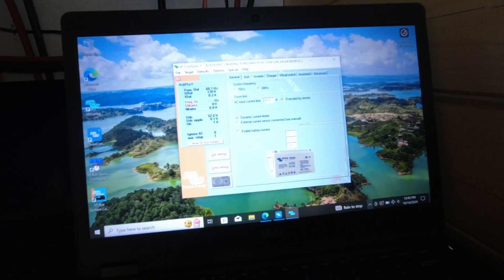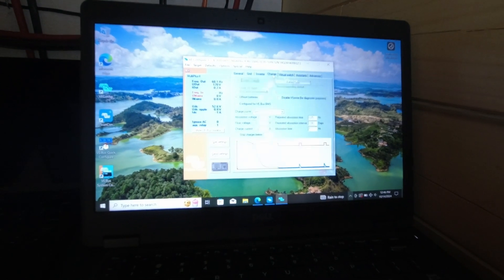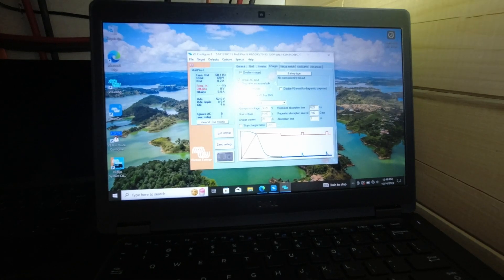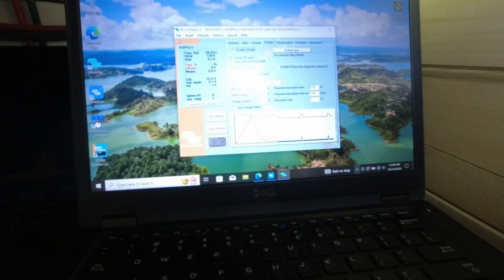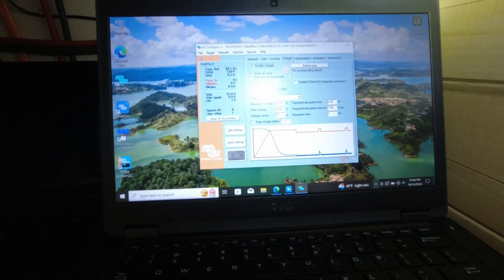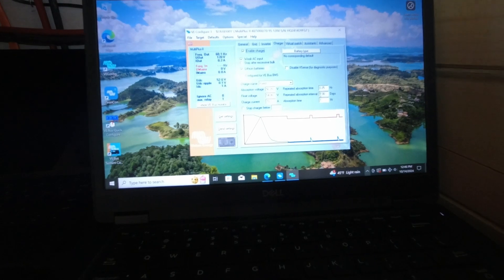They are setting up the cabin as we speak — sorry about all the noise. So here under General, 60 Hz — you can see this is the 20 amps on the second phase, dynamic current limiter. We're not doing anything with grid. Here's ground relay, which is on the slave unit and needs to be turned off; only the master unit should have it active. Let me verify the voltages: I have 54V for float, which is correct, and 56.2V absorption — that's what the EG4 batteries call for. That's correct.